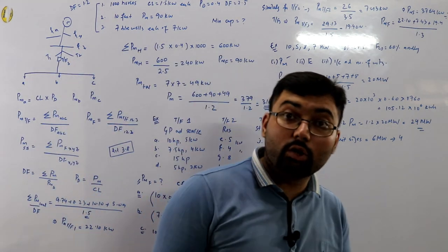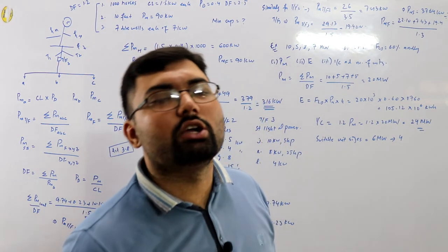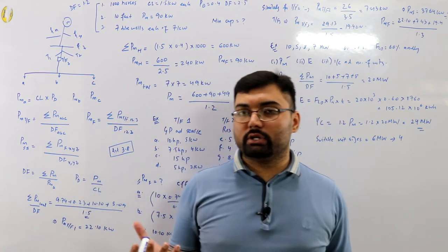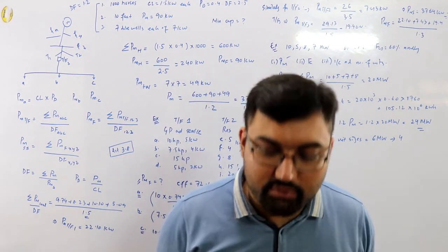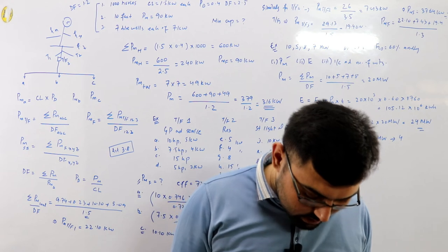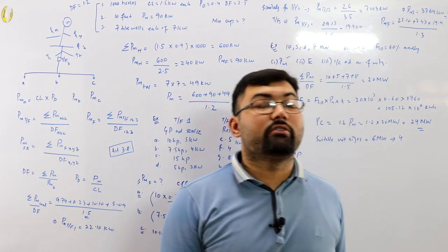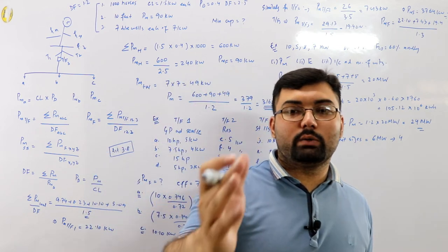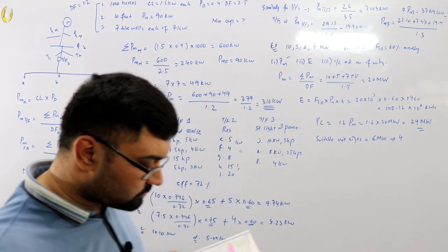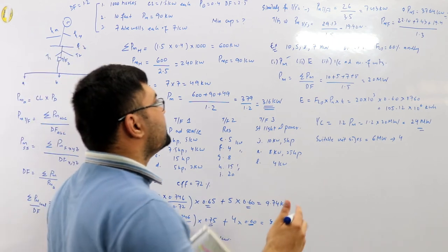A single generating unit would not operate efficiently across a varying load curve, since a machine operates efficiently at about 75–80% of rated power. Multiple smaller units are more practical. Example 3.18 is left as homework — you are given a load curve with time and power values, from which you calculate energy units.